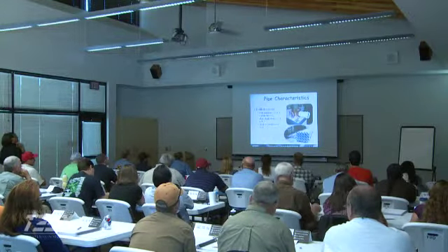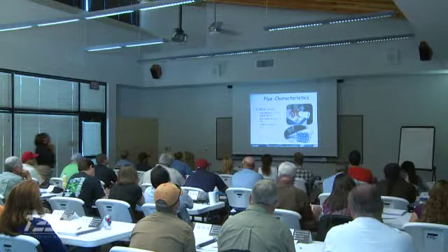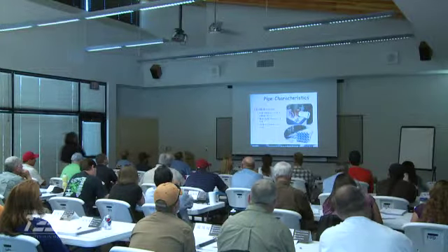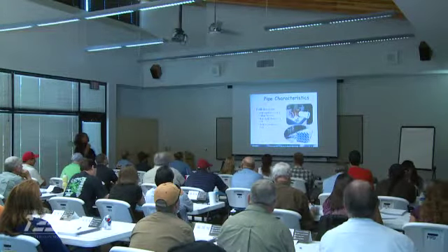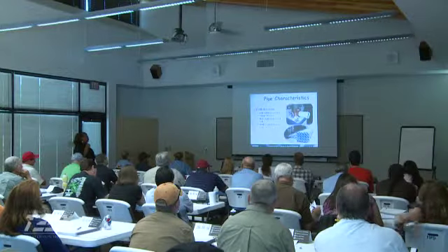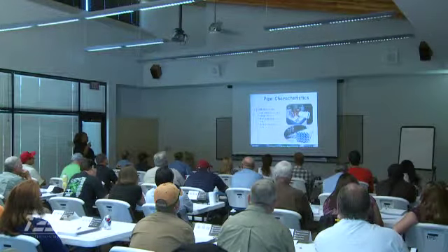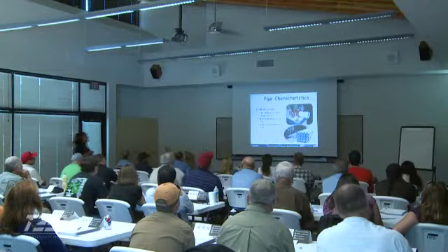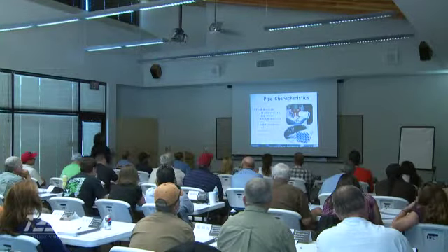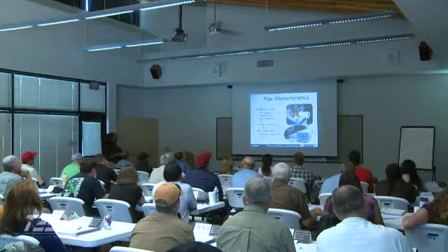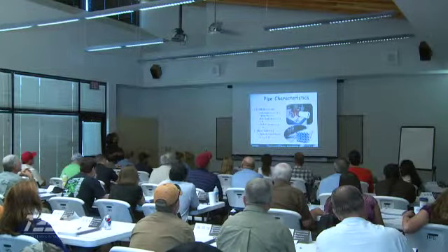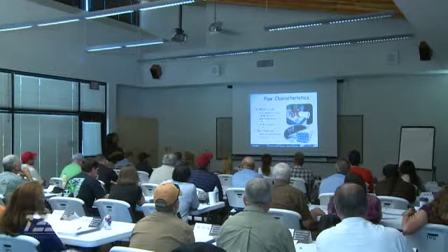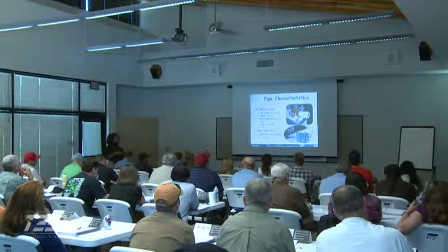Now, published data that's out there, you can also look at the number of connections times P, which will give you a population. Maximum demand, we're looking at maximum daily demands times 2.4 to get that. Peak demand is times 1.25 peak hours. So for the peak demand flows, you go back to this formula here, and I know all of us love math.